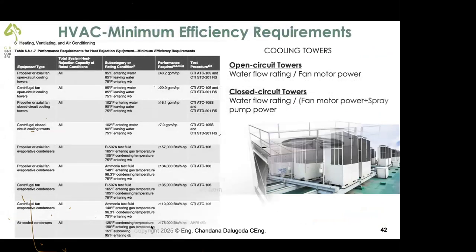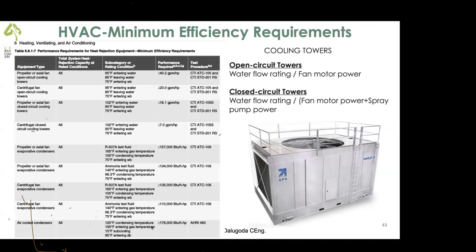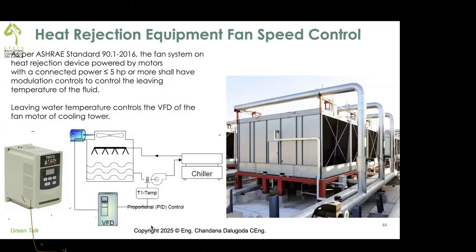If you have a cooling tower, there's an energy performance requirement. Per 1 horsepower, it should deliver 40.2 GPM. That means every 40.2 GPM, 1 horsepower. With 20 GPM, you can't have 1 horsepower. It should be above. That means 50 gallons per minute per 1 horsepower. Yes, that is very efficient. That's how we select cooling towers. Of course, if cooling towers are running 24 hours, you can have variable frequency drives for the fan. How does it work? The controller takes the cooling tower output temperature, and that drives the VFD.